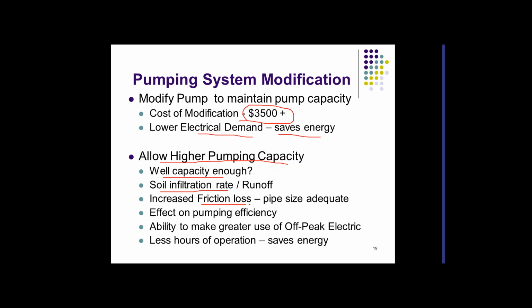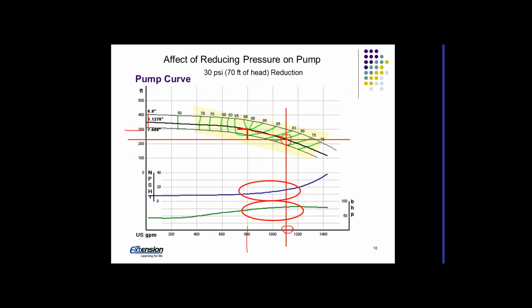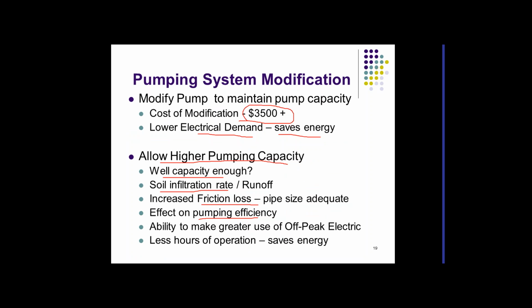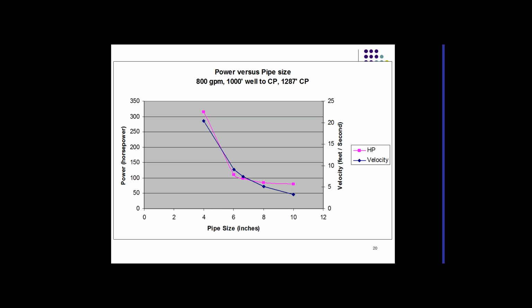But if the water is going through the pipe faster, that could increase friction losses. So we have to make sure we have adequate pipe sizing, and it can throw off the efficiency of the pump. For instance, with this previous one we were operating in an 86% efficient range, but when I drop this down, it's running at an 80% efficient range. That's still a very good range. Anything above 75% is considered very good for a deep turbine pump. Higher pumping rates also, as I said, let us use off-peak electric rates more because I can get the water on faster. And basically where I'm going to save money is that it runs fewer hours to get the same amount of water on. So that's my savings.